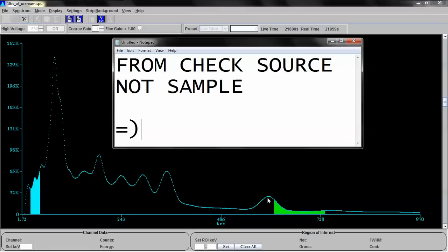And the point I wanted to make with that is you see that green area that was in the other one? It shows a similar area in the other one, and they kind of overlap a little bit. So basically bismuth 214 can throw off detection of cesium-137 big time. In fact, a really poorly calibrated isotope detector could potentially even think it was cesium-137. Bismuth 214 is in every single soil sample I've ever tested. It's really, really commonplace. So anyway, let's get away from this and get into the actual sample.